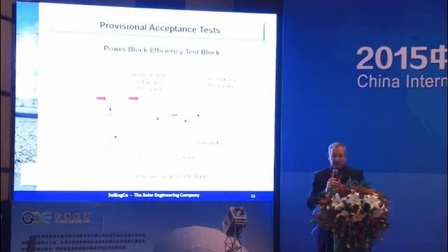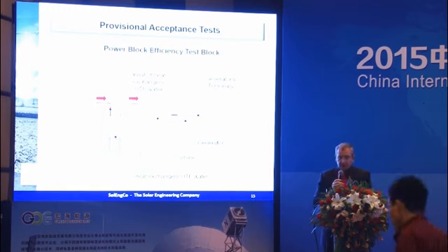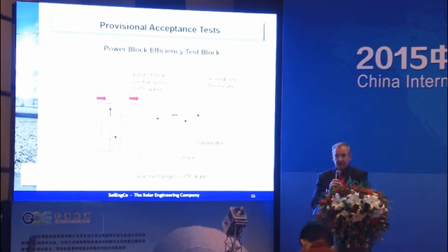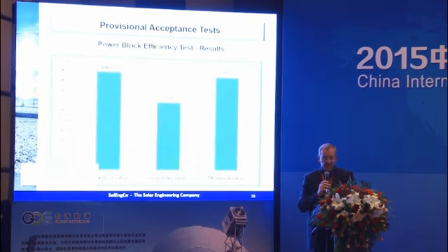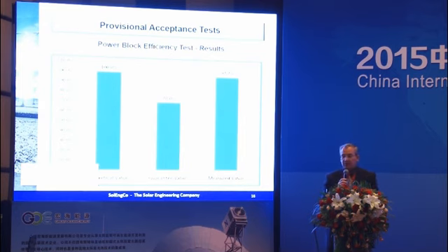Power block efficiency test is a commercial matter, so we measure the energy getting from the solar island, from the HTF heater or thermal storage or solar field, and then we measured the power at the high voltage transformer and the generator. Results show that nearly 100% of the value was reached. It was not such a big surprise like with the thermal energy storage.